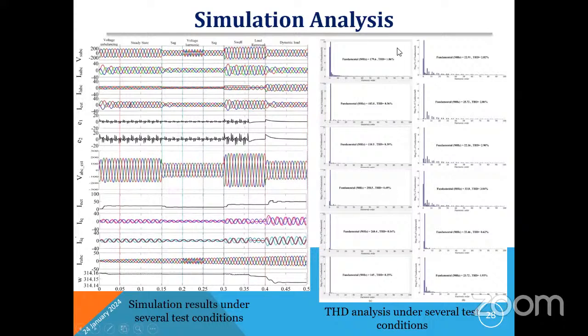If you see the THD analysis of all the test conditions I have given here, in every test case we got less than 5%. This is all 8 conditions. This is voltage THD, and on the left side current THD. If you see all the test conditions, the voltage THD is less than 2%, and the currents I got less than 3%.